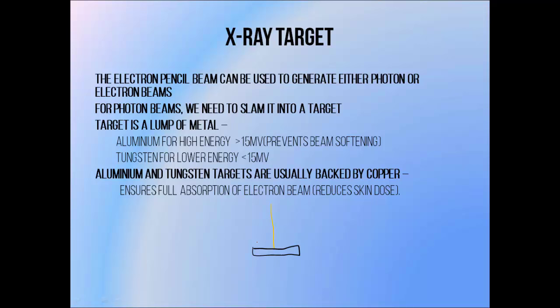If we want to use the pencil beam to generate a photon beam we need to force it to undergo the Bremsstrahlung interaction, so we make it collide with an x-ray target which is essentially a chunk of metal. The Bremsstrahlung interaction becomes more likely as the atomic number of the material increases, so you get more photons per electron with higher atomic number materials. We often use high atomic number materials like tungsten for x-ray targets, which is also a good choice because it is quite durable, and the electron beams used to generate photon beams are quite intense and can cause a lot of damage to soft materials.